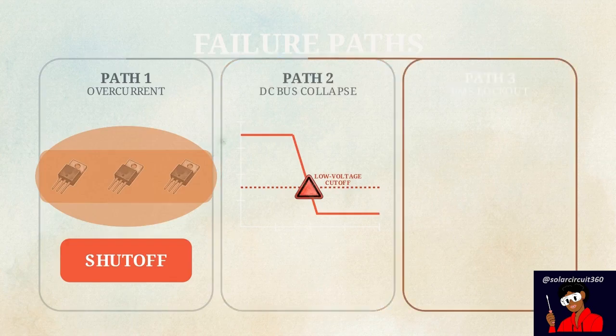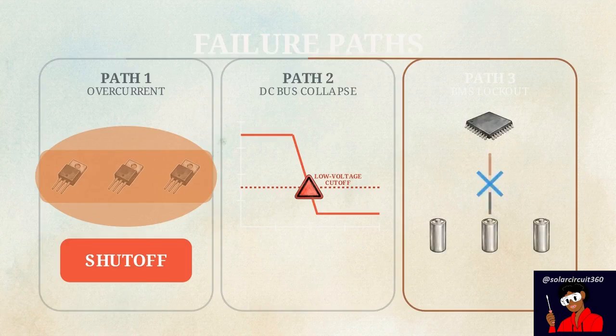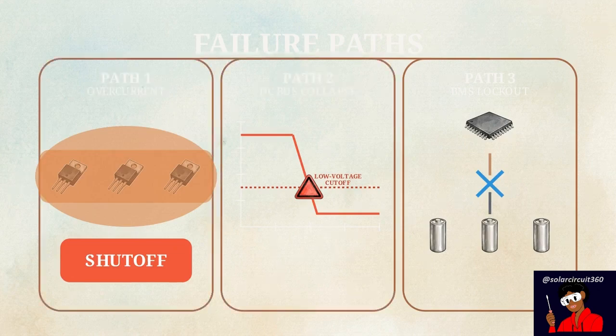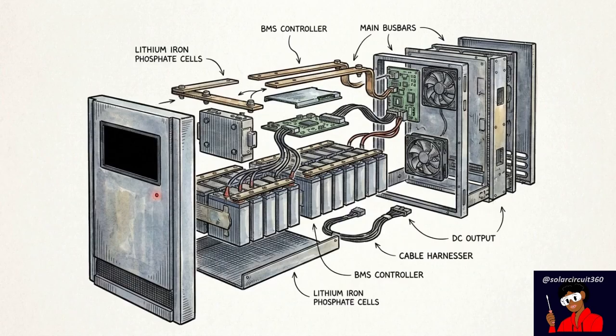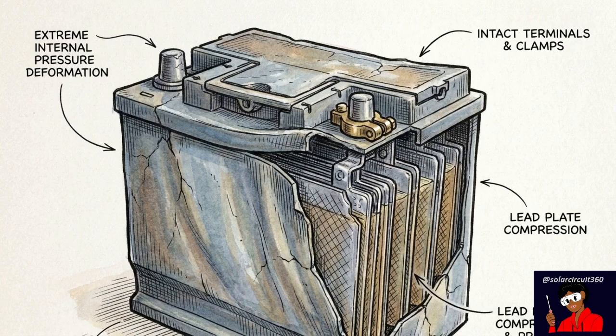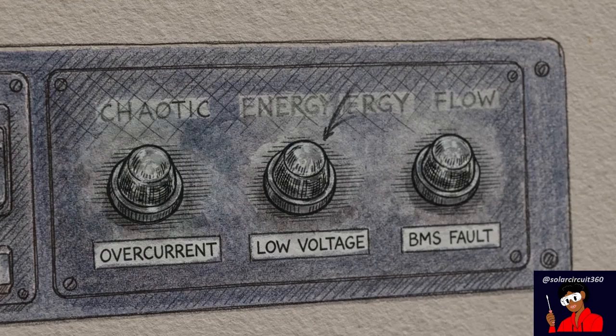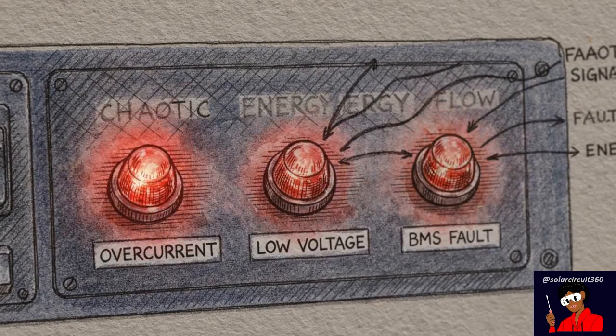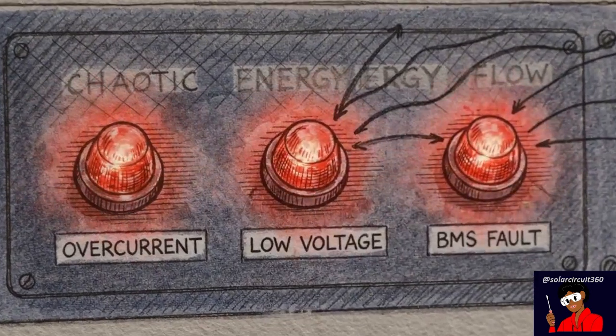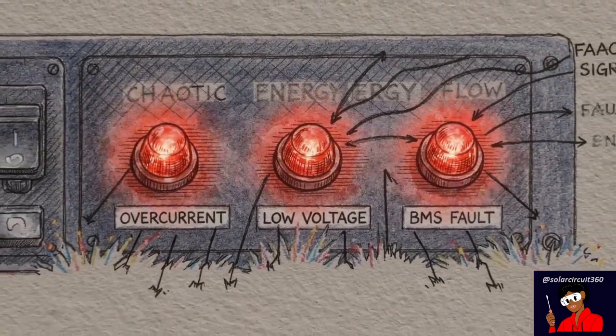The third path is a battery management system lockout. The BMS detects the extreme current flow and instantly severs the connection to protect the internal lithium cells. This lockout is highly common in modern lithium iron phosphate systems, which operate using rigid, instantaneous digital safety limits. Older lead-acid batteries react differently. They sag heavily under pressure, but rarely disconnect themselves completely. During a surge event, all three of these conditions are met simultaneously, racing each other to see which protection trigger will fire first.